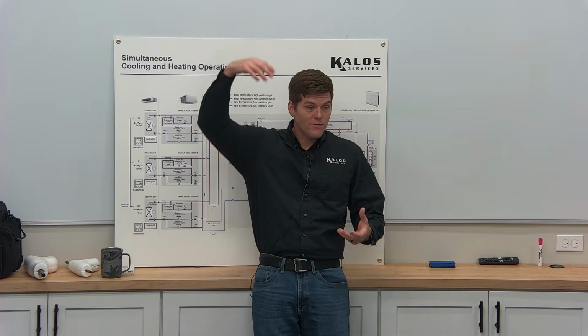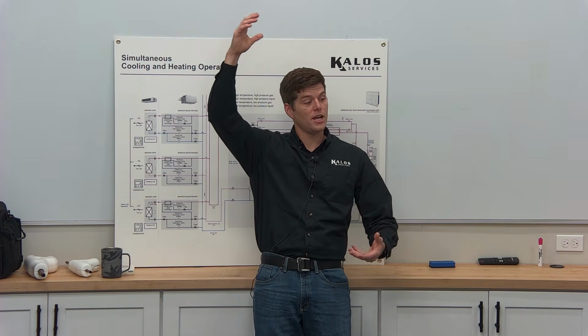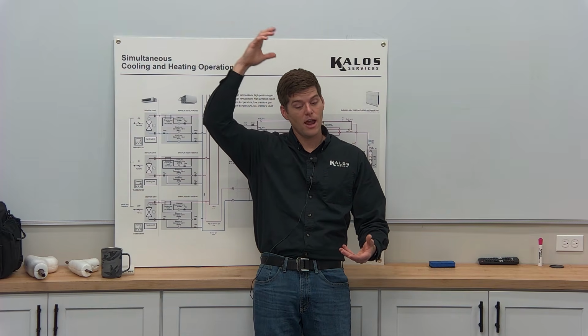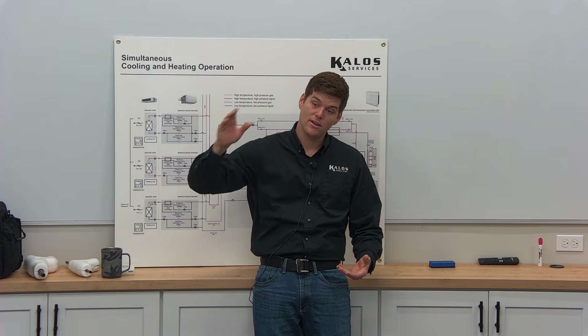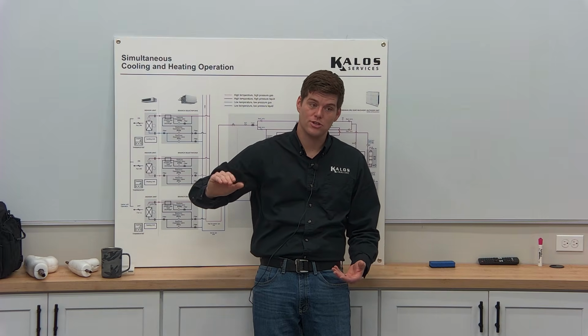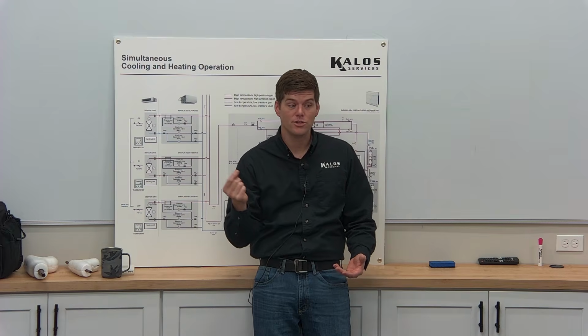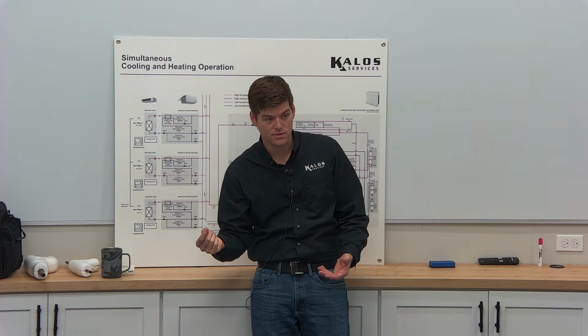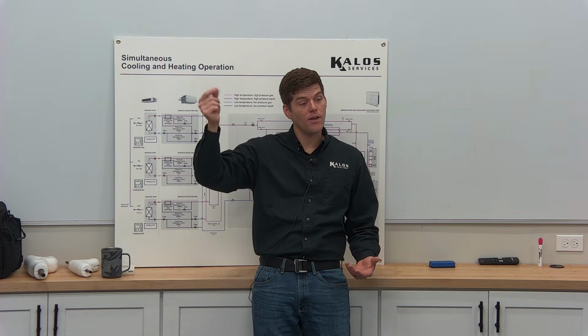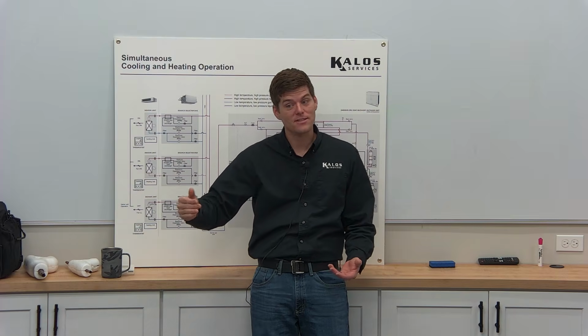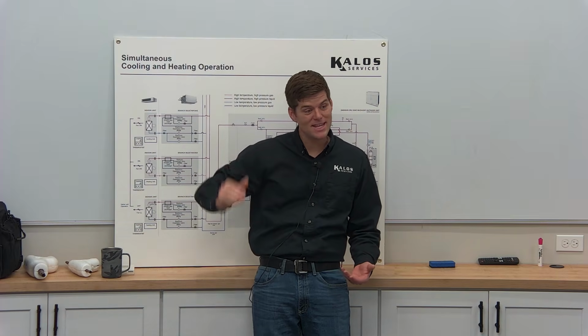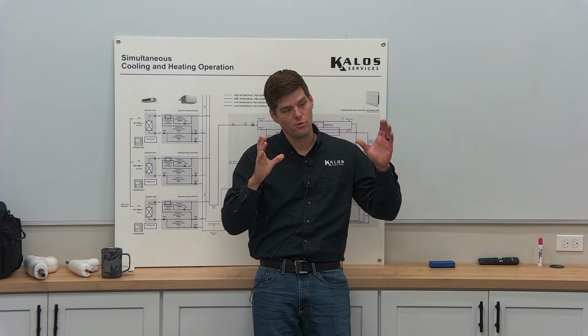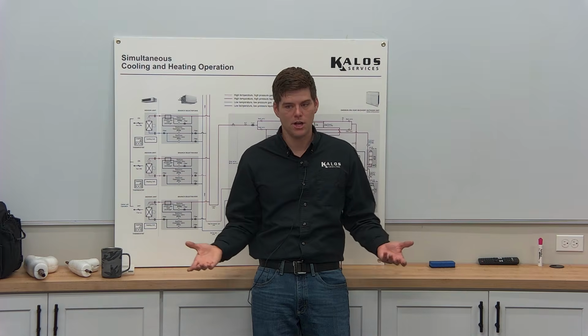It takes that DC voltage that it's charged up in these giant capacitor banks on the boards, and then it trickles it, right? Using pulse width modulation to actually run the compressor at a lower hertz than 60 hertz, and then speed it up, and then speed it down. And it has up to 168 different speeds in that up and down from that inverter board itself. So that's where the variable comes from.